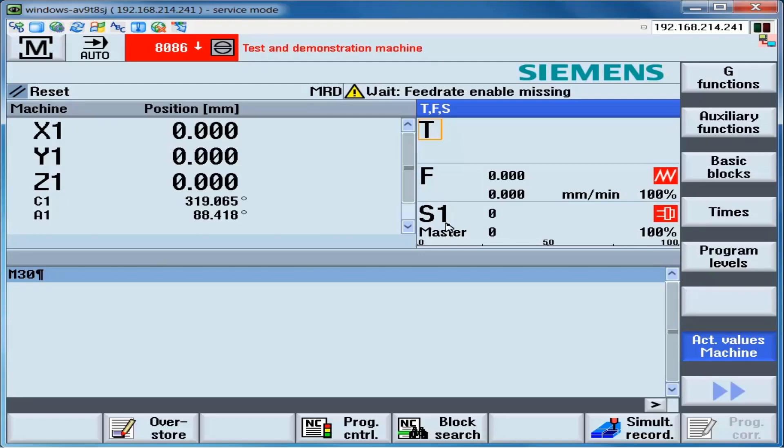Synchronous motors with incremental encoders and reference pulse require a certain synchronism between the encoder and rotor when the reference pulse is used for fine synchronization. Siemens standard 1FT, 1FK, and 1PH synchronous motors are synchronized at the factory and no additional intervention is necessary.